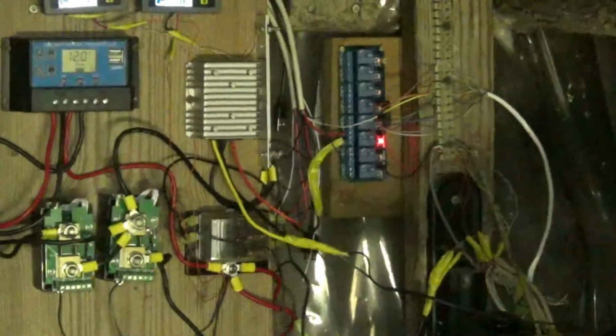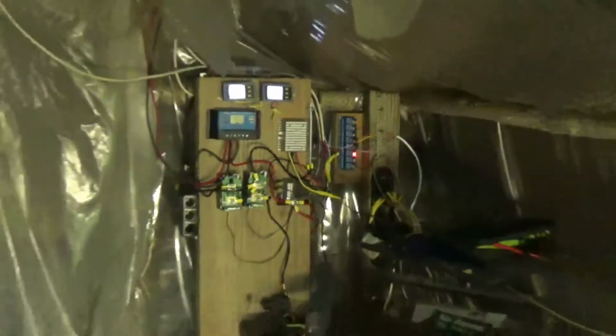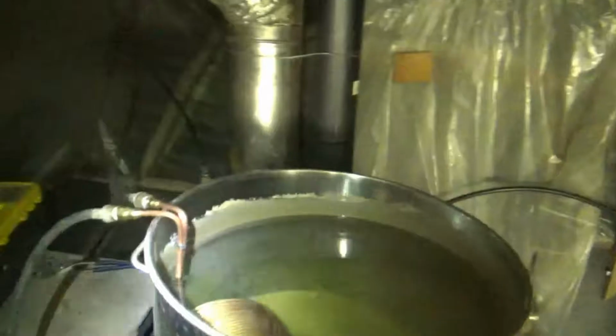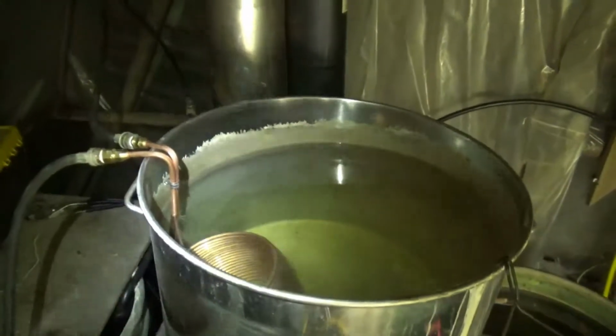You can see right now the temperature difference between the two tanks is greater than 40 degrees, and that relay is on - you can tell because only the relay with the red light is connected at the moment. You might be able to hear the pump running, but it is running, I assure you.